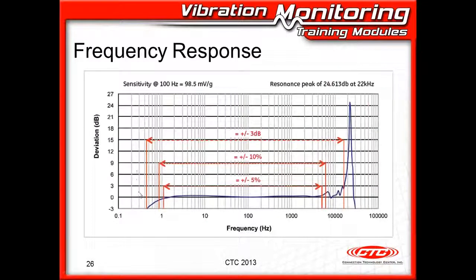And I've charted that for us so that you can see that on the plus and minus 3 dB, it goes from the min to the max limits that are usable, but it also has the largest variation in amplitude. So plus or minus 3 dB, and so we'd have quite a bit of variation here at the higher end, and then you can see that it rolls off at the lower end. On plus or minus 10%, we tighten up on the amplitude a little, but we also lose low frequency and we lose high frequency response to keep that amplitude tighter. And on plus or minus 5%, we've got some real tight amplitude tolerances, but again, we've given away frequency on the low end and on the high end.